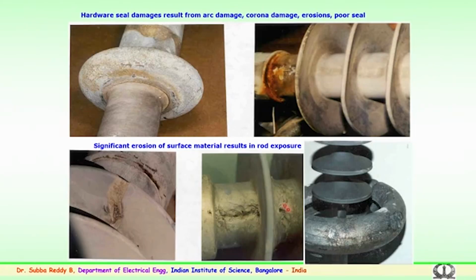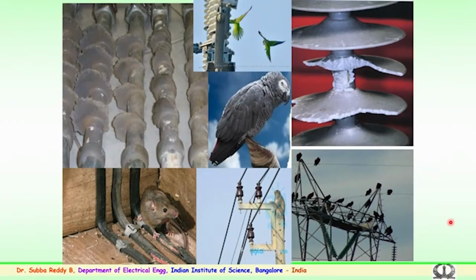Likewise, these are failures because of the end fittings, the hardware which is employed for the polymer insulators, and also this is a corona control ring for the non-ceramic insulator or polymer insulator. Over a period of time, if this insulator is not properly designed and not properly oriented and placed, it could lead to continuous discharges, and these discharges on the surface of the insulator could completely damage the hydrophobicity effect on the insulator and could lead to failures. So, these are some of the various failures which have happened because of electrical stress, mechanical and corona related issues.